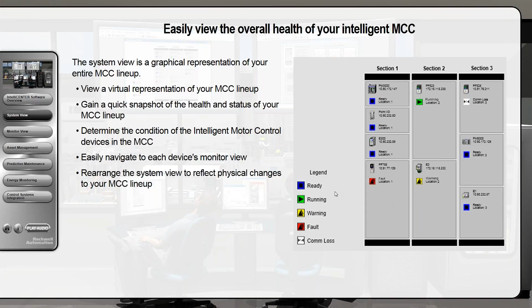First and foremost, the system view: where are your devices located, where are your sections, and what are those devices? We have our system view, sometimes called the elevation view, that provides readily available descriptive analytics for each device in each unit and section location. We have a legend for each device in each area to designate if there's a fault, a warning, or if everything's running and ready to go, even a comm loss, which is extremely important. So you can gain a quick snapshot of what's going on in your MCC and determine if you need to take further action and navigate to those devices specifically.